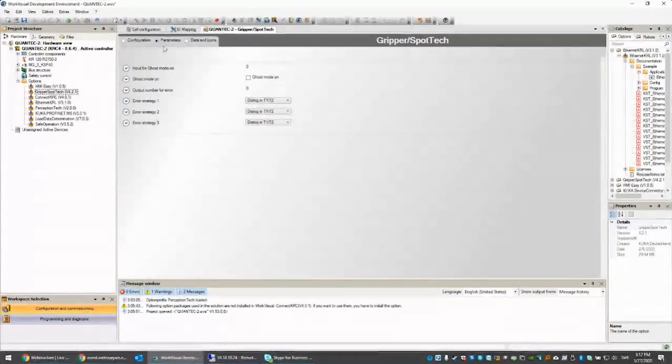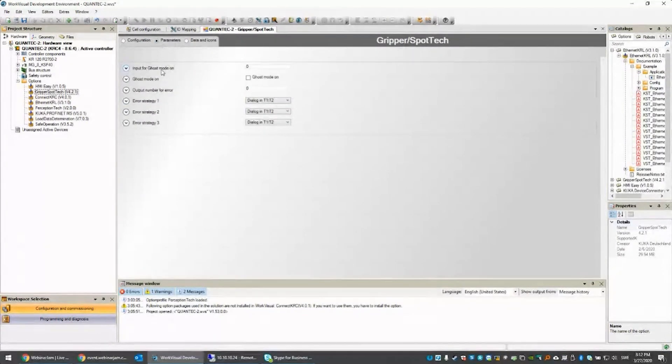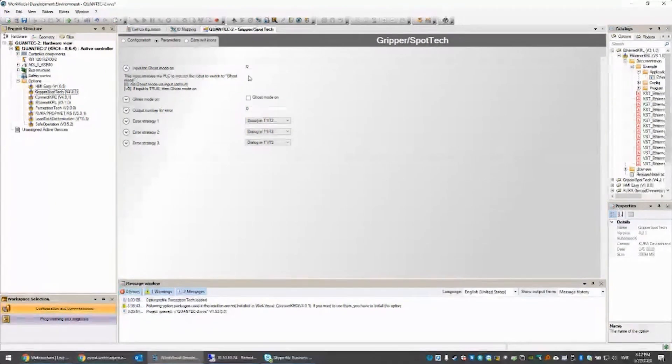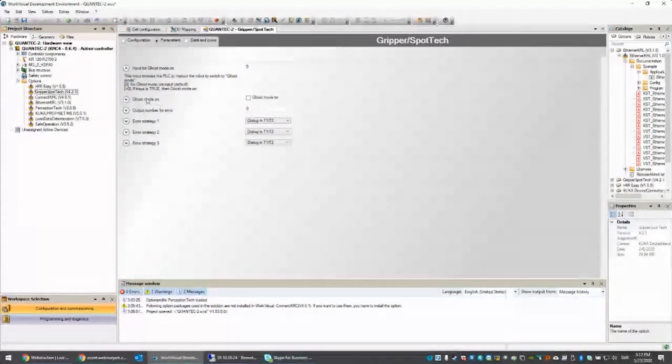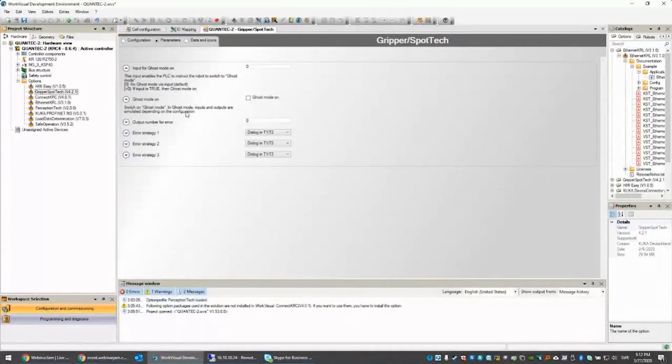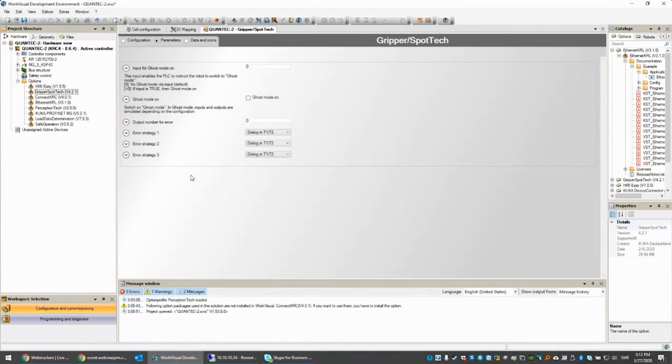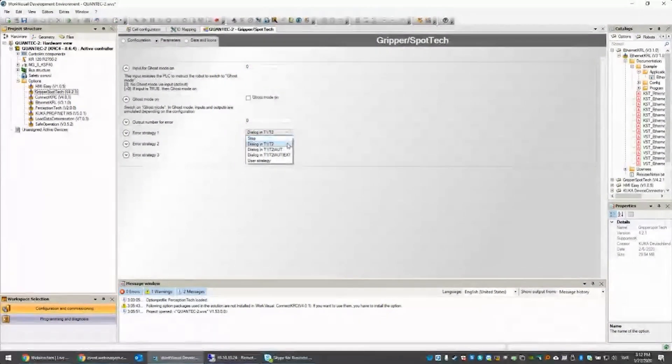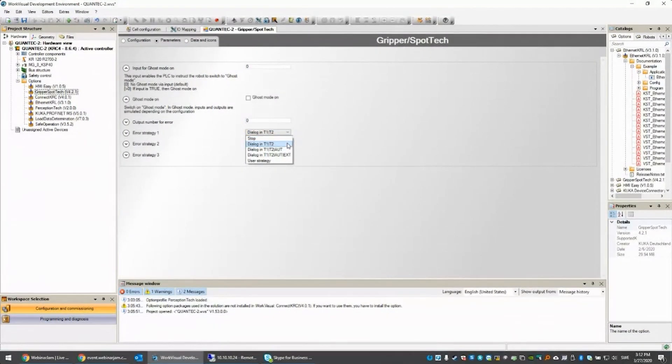Next is the parameters. We have something called ghost mode that can be enabled from input from the PLC. In ghost mode, inputs and outputs are simulated depending on the configuration. If I have an error, I can set an output for errors, so the higher level control knows there's an error.